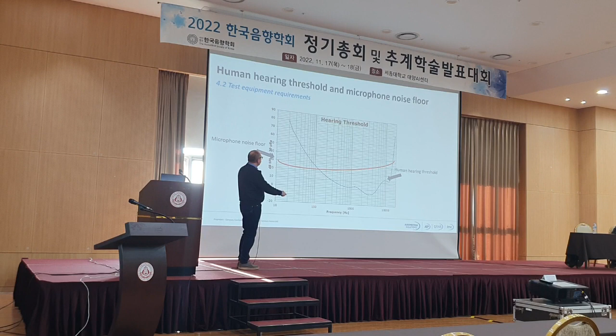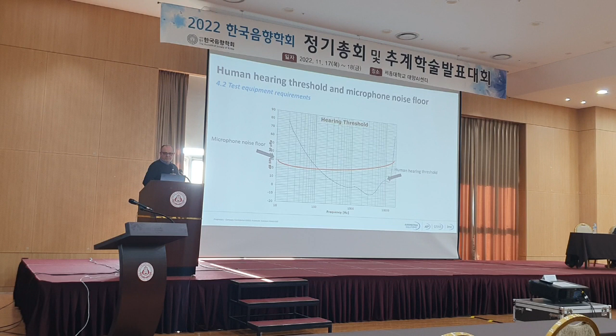But what we need to look at is another important factor for the ear coupler, the threshold or the microphone noise. Normally, a human ear can hear down to around 0 dB. And you remember, 0 dB is not zero noise. 0 dB is the limit of what the human ear can hear. But we can measure below that. And the problem is that a normal measurement microphone has a noise floor around up here. So we cannot measure with a normal microphone the same levels that humans can hear.